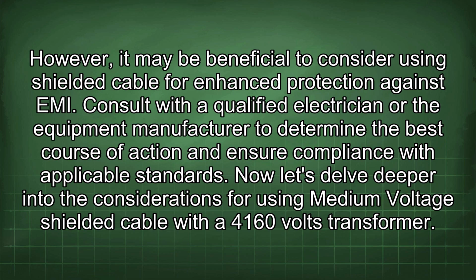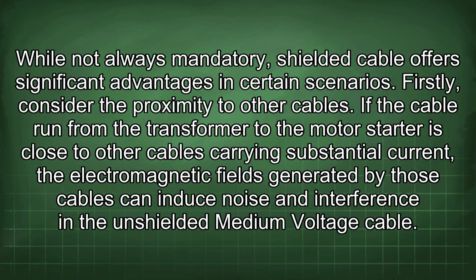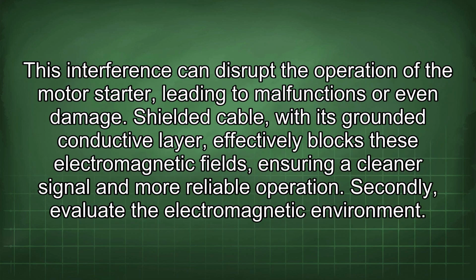Now let's delve deeper into the considerations for using medium voltage shielded cable with a 4160 volts transformer. While not always mandatory, shielded cable offers significant advantages in certain scenarios. Firstly, consider the proximity to other cables. If the cable run from the transformer to the motor starter is close to other cables carrying substantial current, the electromagnetic fields generated by those cables can induce noise and interference in the unshielded medium voltage cable. This interference can disrupt the operation of the motor starter, leading to malfunctions or even damage. Shielded cable, with its grounded conductive layer, effectively blocks these electromagnetic fields, ensuring a cleaner signal and more reliable operation.